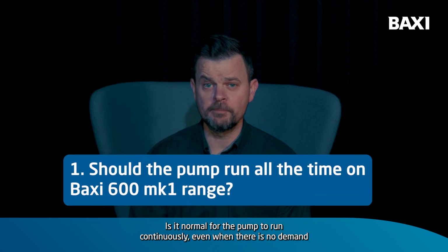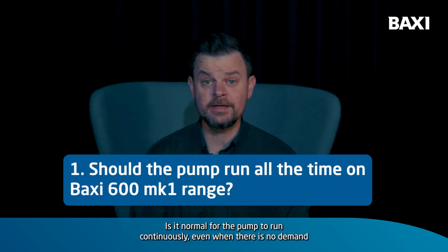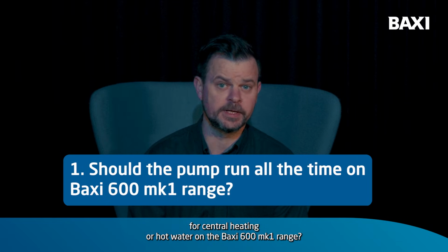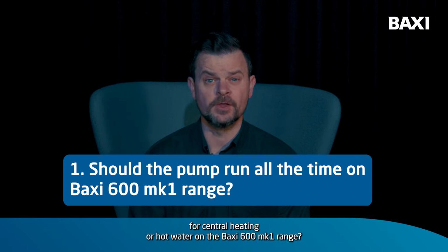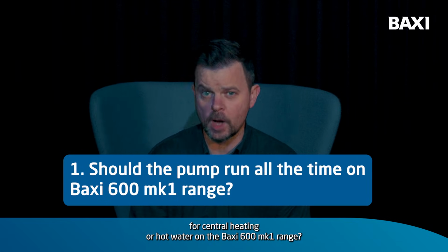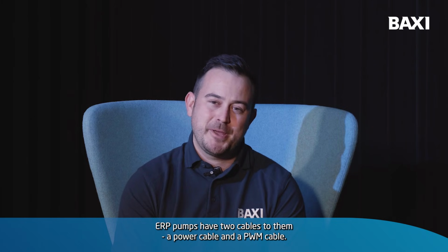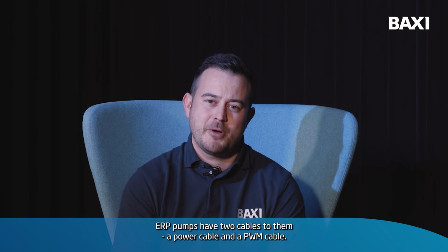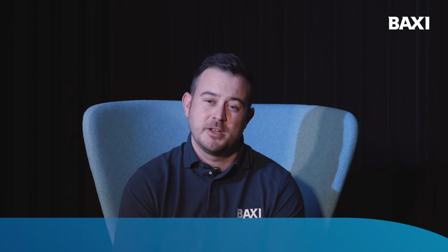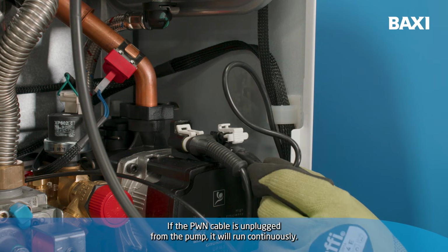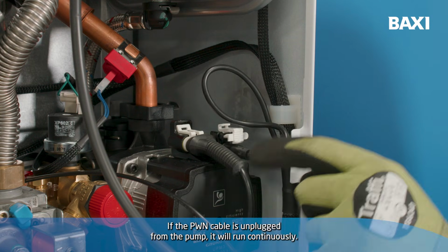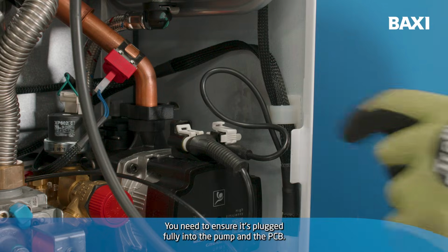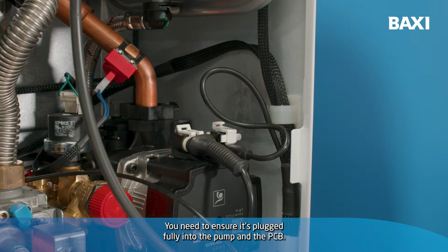Question number 1. Is it normal for the pump to run continuously even when there is no demand for central heating or hot water on the Baxi 600 Mark I range? Our ERP pumps have two cables to them, a power cable and a PWM cable. If the PWM cable is unplugged from the pump, it will run continuously. You need to ensure it's plugged fully into the pump and the PCB.